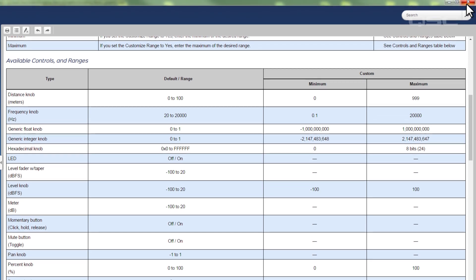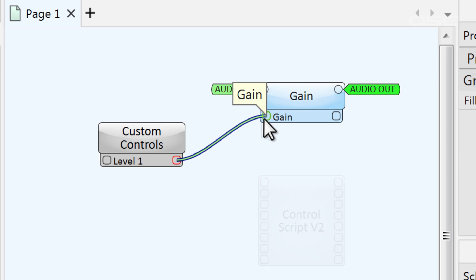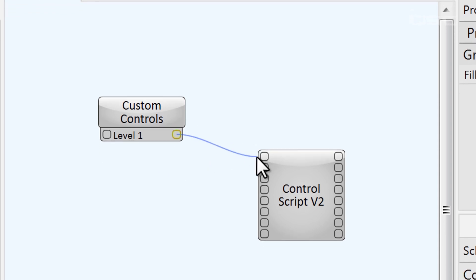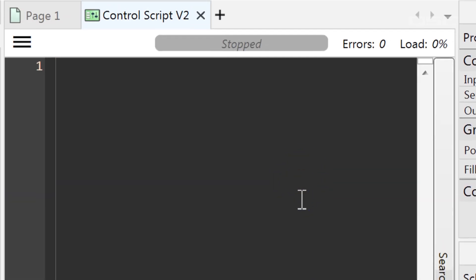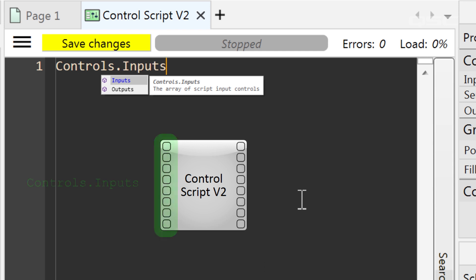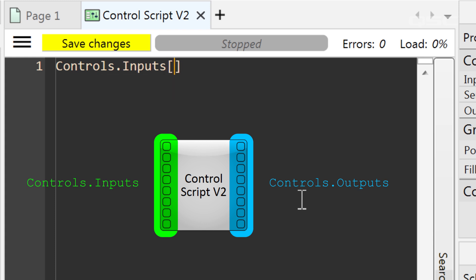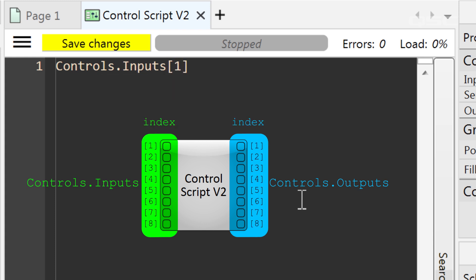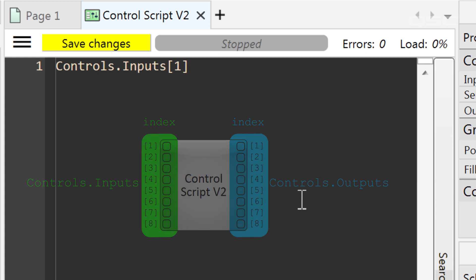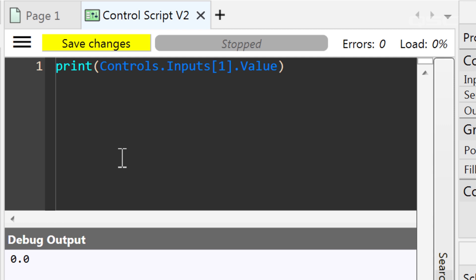If you're using control components, you can start wiring these custom controls directly to whichever control pins you like. If you're using the control script component, you can wire these to your script. You can then reference that control within the script by using the keyword controls, which is the main object of the control tree — in this case, controls.inputs or controls.outputs, depending on where it's wired. You'll also need to note which pin it's connected to in a bracket, known as its index. You could then extend this control tree to reference a specific property of the control. Using the print command, you could print the control's value to the debug window with: print(controls.inputs[1].value).